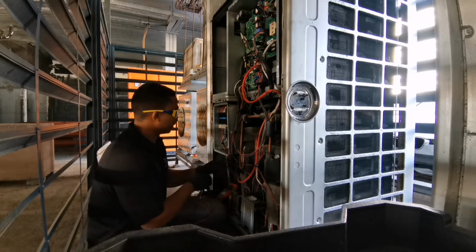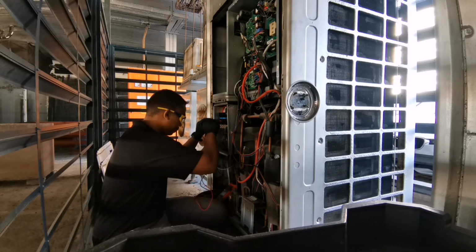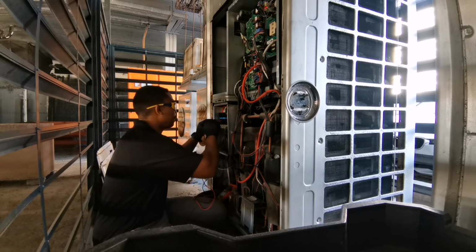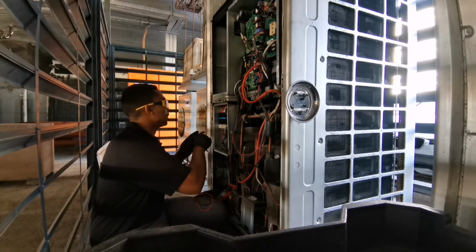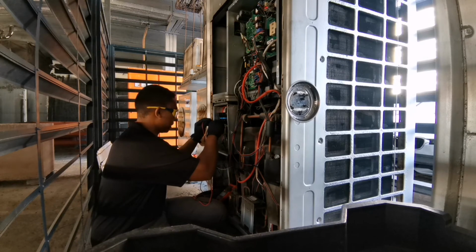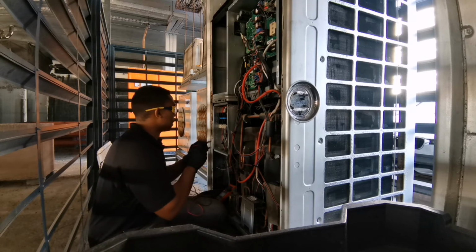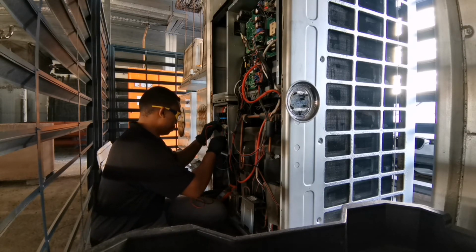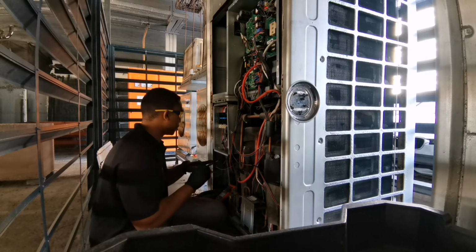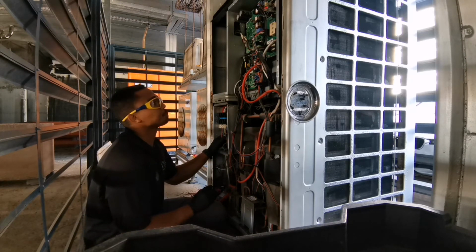Alright, apply 1 to 1. Got 395, 396, 399. Check the neutral. Neutral to 1, 229, 230, 238. Alright, check the voltage leakage. Good. We are good. Incoming supply is good.